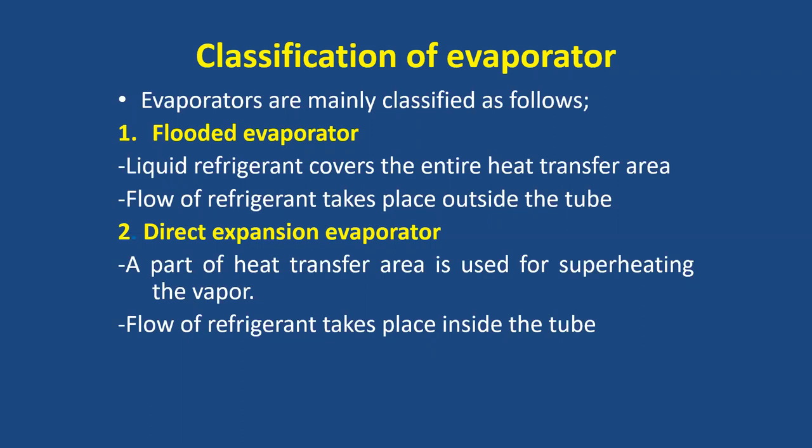Flooded itself has a meaning: the heat transfer area is flooded with refrigerant. And the flow of refrigerant takes place generally outside. So the moment we say flooded, it means the tube is flooded with the refrigerant. Generally in a flooded evaporator, the evaporation is taking place outside the tube. And if it is taking place inside the tube, then almost the entire heat transfer area is covered with the liquid refrigerant. So with flooded, there are both possibilities, evaporation inside the tube as well as evaporation outside the tube.